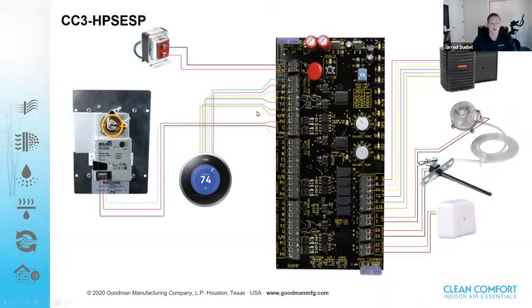So first of all, we have a little Nest thermostat wired up here. Again, you have your hot and common, your W for heat, your Y1, Y2 for first and second stage cooling, G for your fan, OB for your reversing valve, and then you're going to have power closed, common, and power open for your 3-wire damper. Now, one thing that I will make mention of here on this ESP panel, you have to have 3-wire dampers for the ESP function to work.